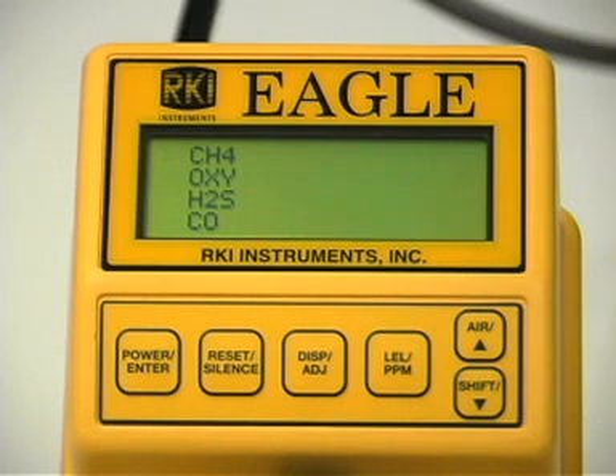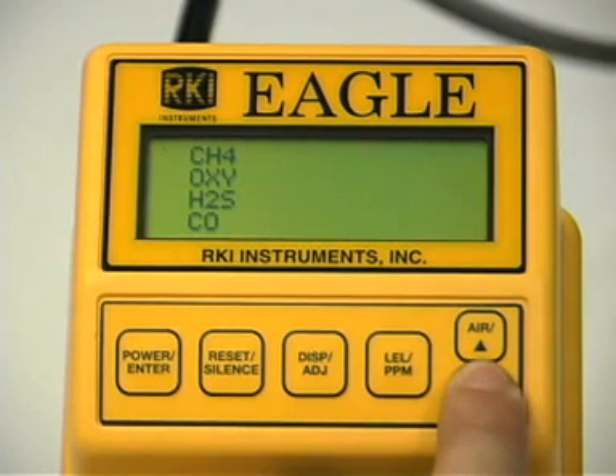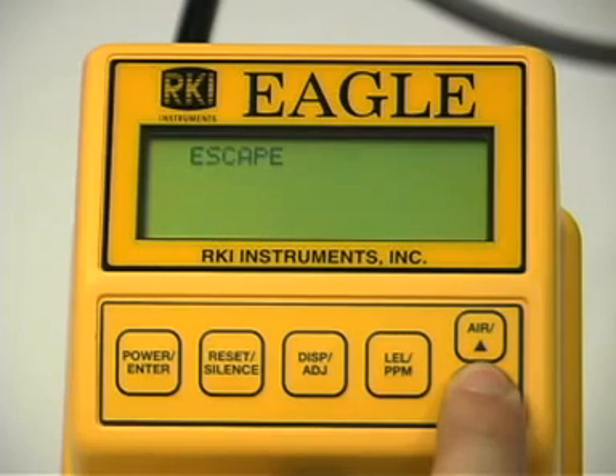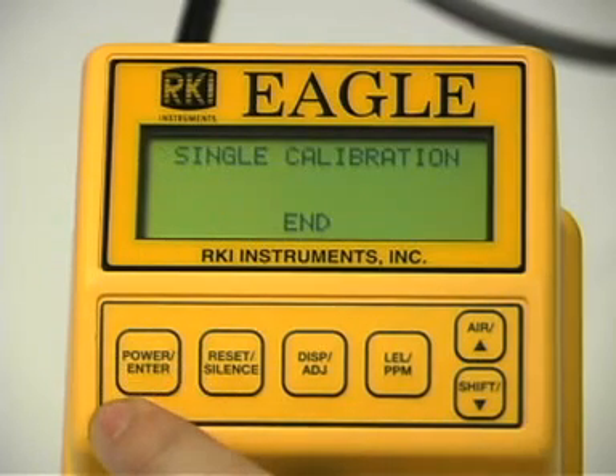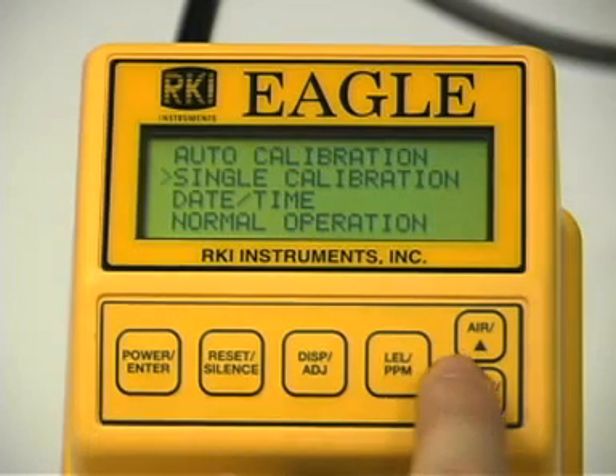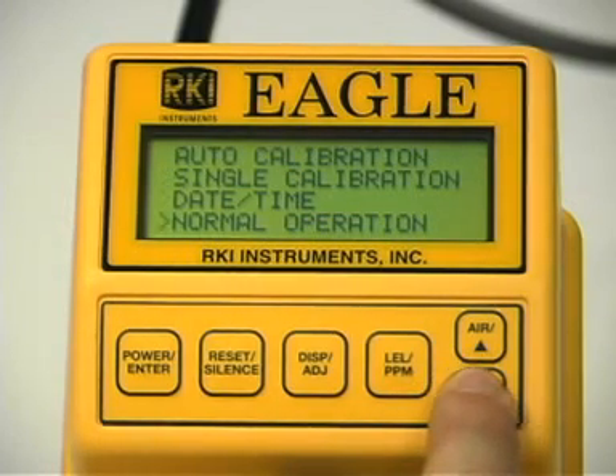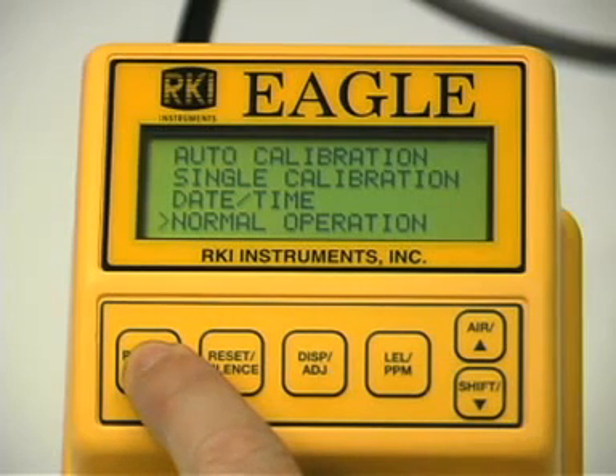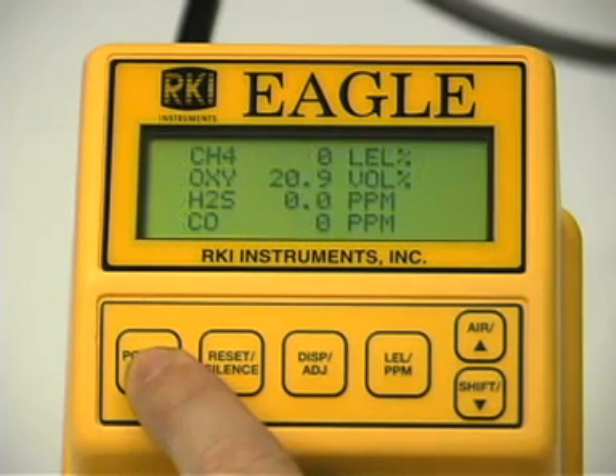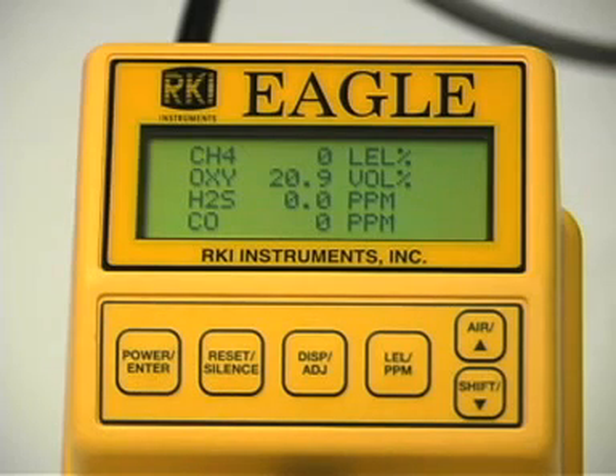With the single calibration menu displayed, press the down button until the prompt is next to escape on the display and press the enter button. Now scroll down to place the prompt next to the normal operation menu option and press the enter button to return the Eagle to normal operation. The single calibration method does not have a fail notification, so you should replace sensors that cannot be set to agree with the calibration source, then recalibrate.